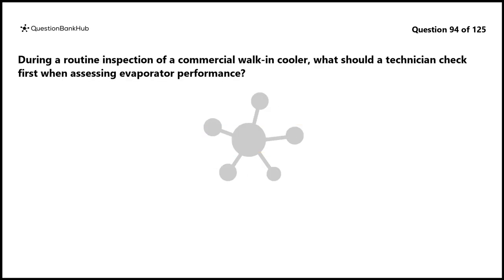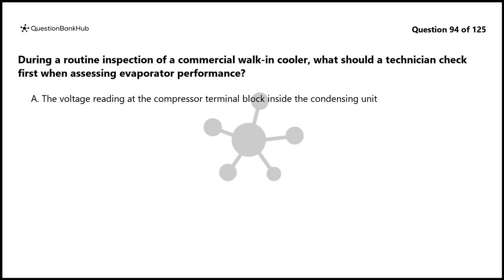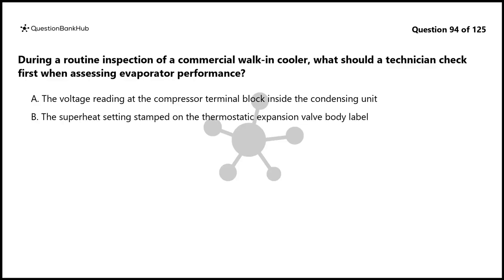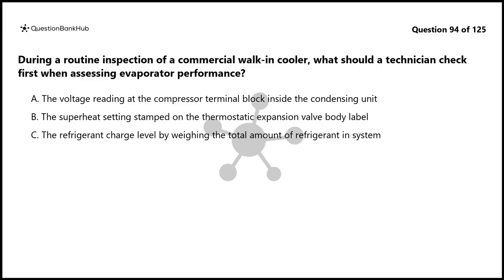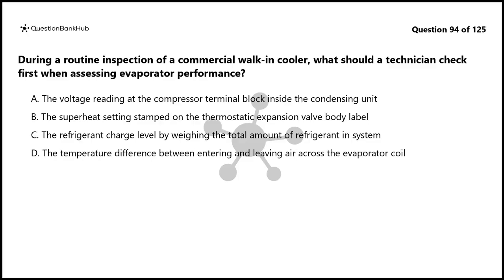Question 94. During a routine inspection of a commercial walk-in cooler, what should a technician check first when assessing evaporator performance? A. The voltage reading at the compressor terminal block inside the condensing unit. B. The superheat setting stamped on the thermostatic expansion valve body label. C. The refrigerant charge level by weighing the total amount of refrigerant in the system. D. The temperature difference between entering and leaving air across the evaporator coil.